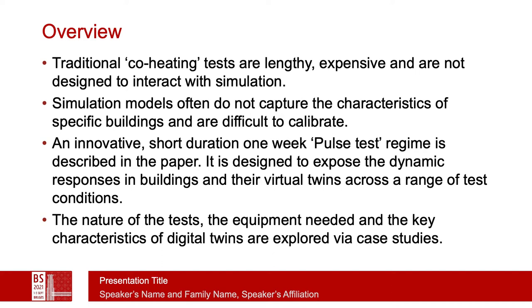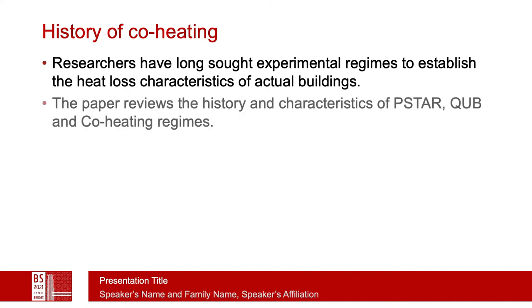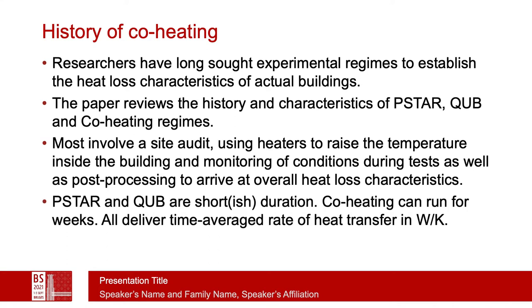The nature of the test, the kit needed, and key characteristics of digital twins are explored. Although co-heating has continued for a considerable time due to the need to establish actual heat loss characteristics in buildings — the performance gap — in the paper we review the history and characteristics of several methods, including PSTAR, QUB, and co-heating. Most involve a site audit and the use of heating or cooling devices to maintain a particular set point under varying external conditions, with post-processing to arrive at overall heat loss characteristics. Some tests are short duration; however, co-heating itself can run for many weeks to deliver time-averaged heat transfer.